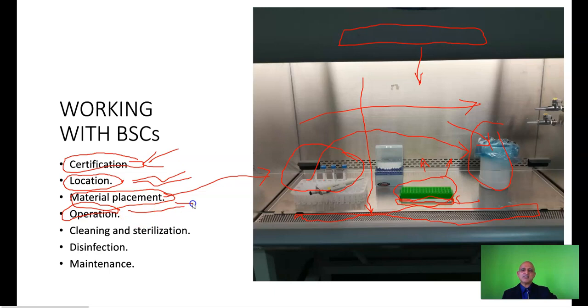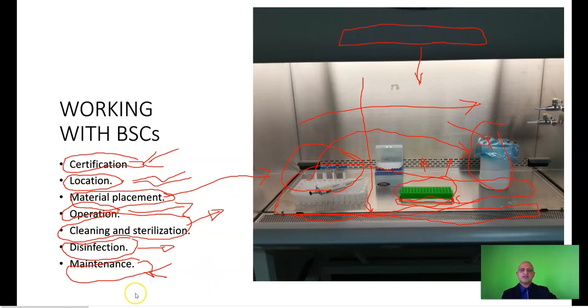For instance, in my facility, I may have a procedure for decontamination prior to use using ultraviolet light for a duration of 20 minutes, followed by a surface wipe down and a decontamination post usage. And this is stated in the cleaning and sterilization standard operating procedures which accompany this BSC. Finally, there are specific protocols for disinfection in case of a large spill. This section can actually be removed, and then you can clean the area below and disinfect it with a specific agent and with the specific contact time. And finally, there's the maintenance schedule. So you have breakdown and periodic maintenance in your SOPs.